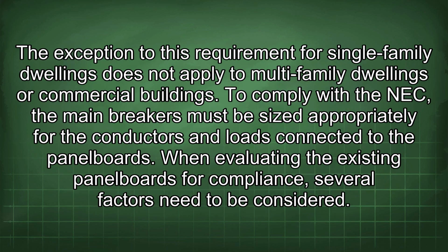board. The exception to this requirement for single-family dwellings does not apply to multi-family dwellings or commercial buildings. To comply with the NEC, the main breakers must be sized appropriately for the conductors and loads connected to the panel boards. When evaluating the existing panel boards for compliance, several factors need to be considered.